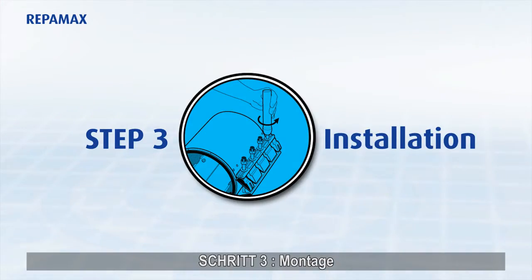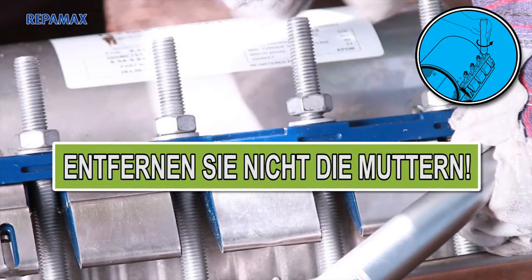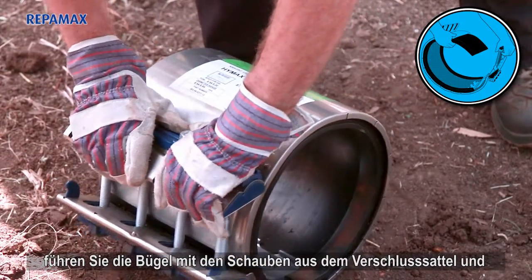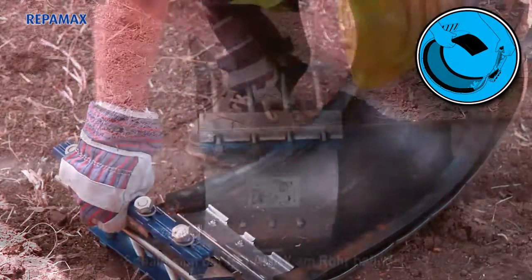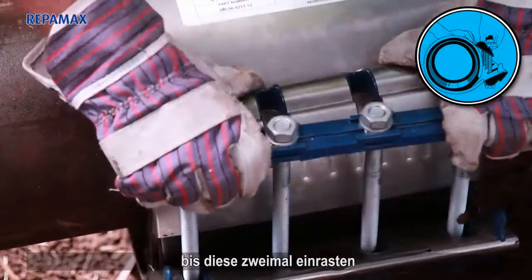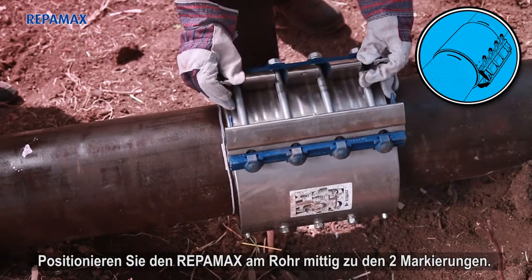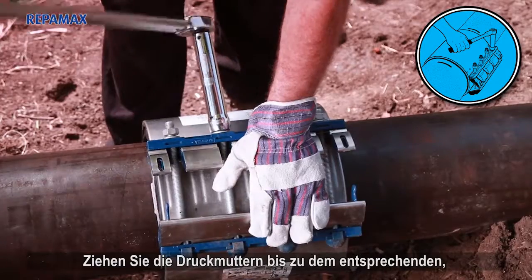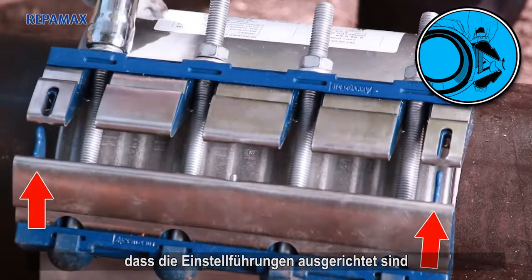Step 3: Installation. Open the Repamax by loosening the nuts — do not remove the nuts. Partially compress the lug assembly, pull upwards on the lug compression beam, and unlatch the lug assembly allowing the Repamax to extend to a fully open position. Once the Repamax is around the pipe, re-engage the compression beam over the lug assembly until it clicks in place twice. Position the Repamax around the pipe centered between the two marks. Tighten the bolts according to the specified torque using a torque wrench. Tighten the compression nuts to the proper torque as indicated on the product label, making sure the adjusting guides are aligned.